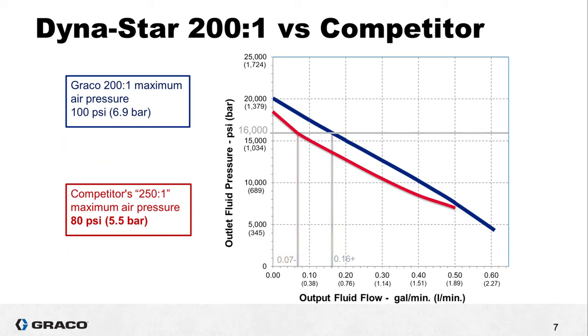We could do the same thing at 10,000 psi outlet pressure. There's already this dotted line but let's make it more clear. The competitor's curve hits the line just past 0.31 GPM and ours is right around 0.41 GPM at 10,000 psi so about one-third more flow.